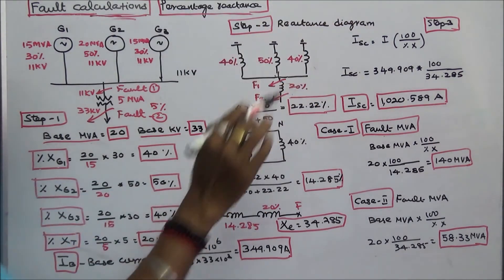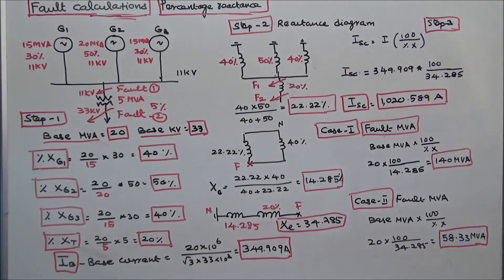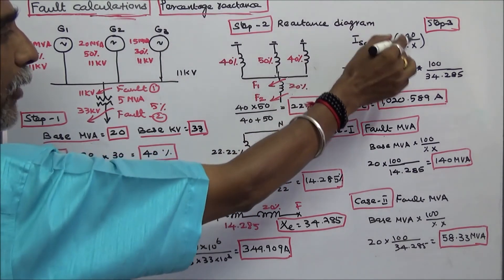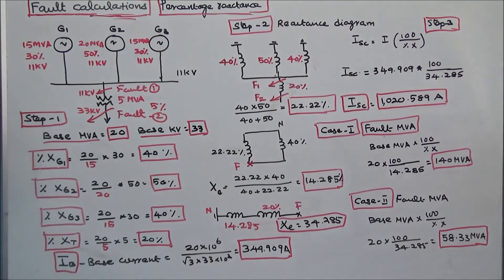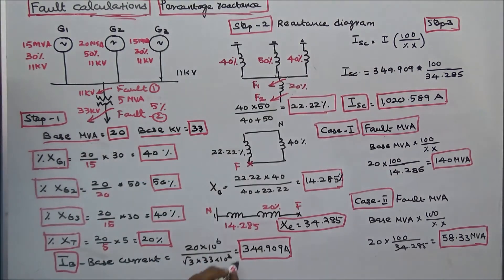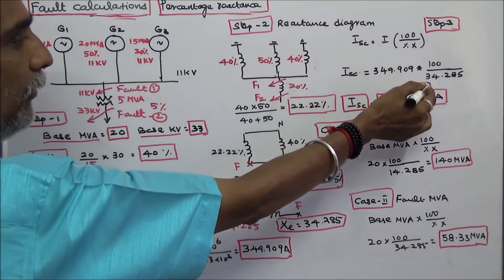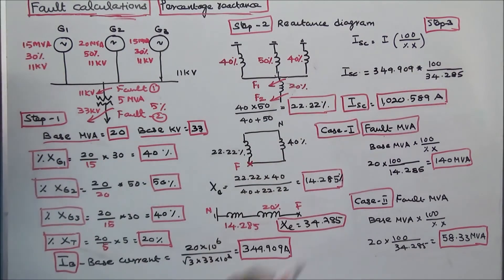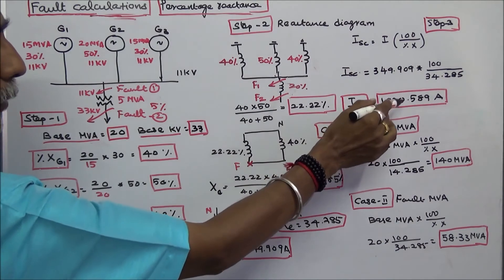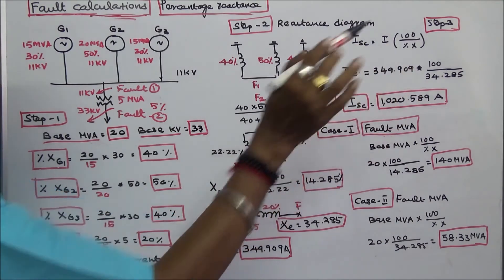The third step is to calculate the short circuit current. Short circuit current ISC is equal to rated current I × 100 divided by percentage X. Therefore, ISC = 349.909 × 100 / 34.285, which gives a short circuit current of 1020.589 amps.